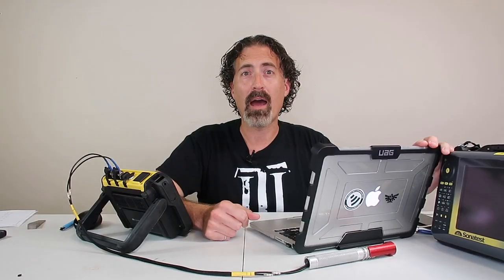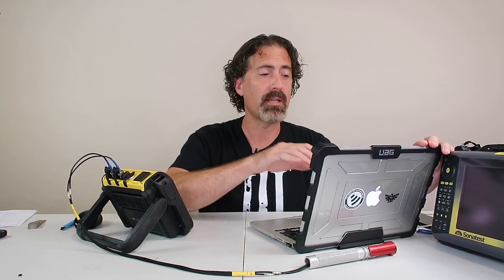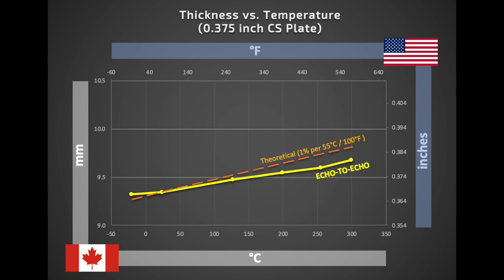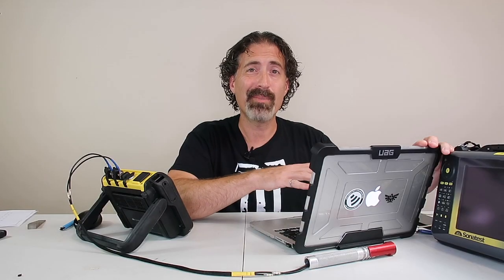Now let's make a graph of how the thickness changed with the temperature. Now the first thing you see here is the echo to echo readings, my yellow line, the ones we just did. They line up pretty close with the theoretical. It's maybe not quite 1% for every 55 degrees, but it's close.